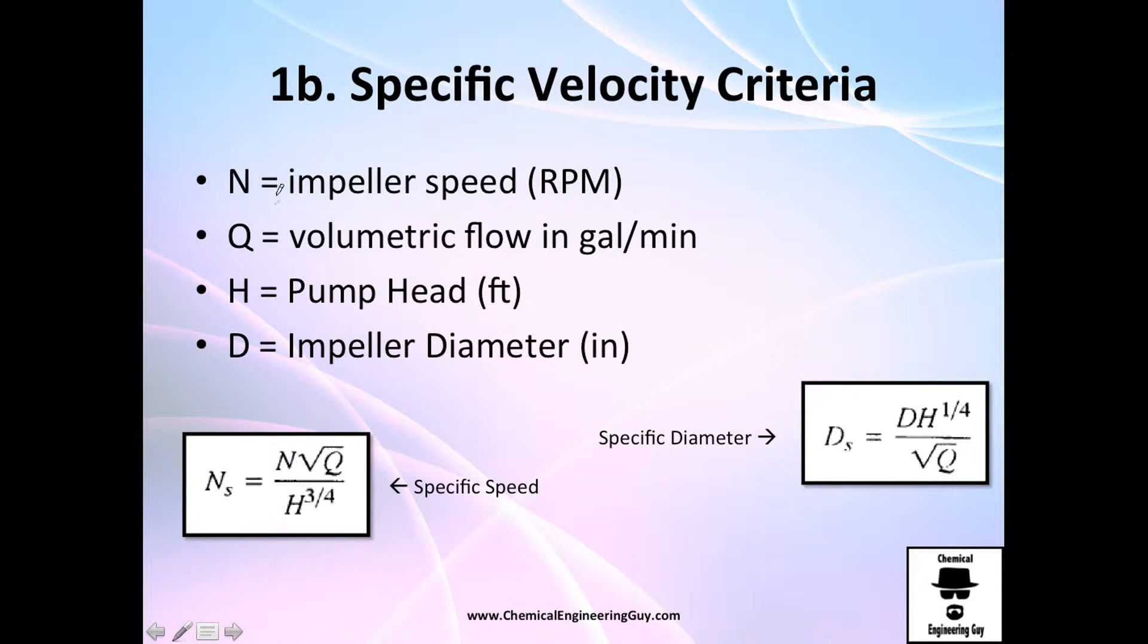So recall, N is the impeller speed in revolution per minute, Q is the volumetric flow in gallon per minute, H is the pump head in feet, and D is the diameter of the impeller in inches. The equation for specific speed is N times the square root of the volumetric flow rate divided by H to the three-fourth powers. And this one goes for specific diameter.